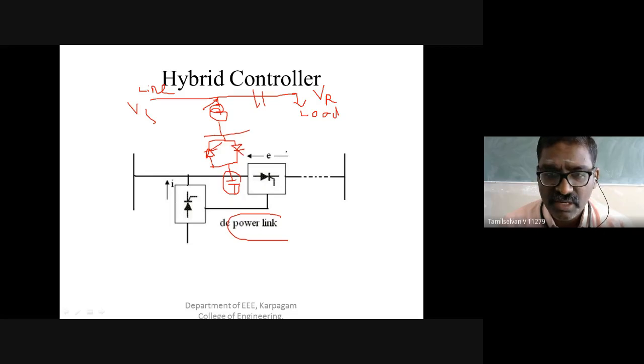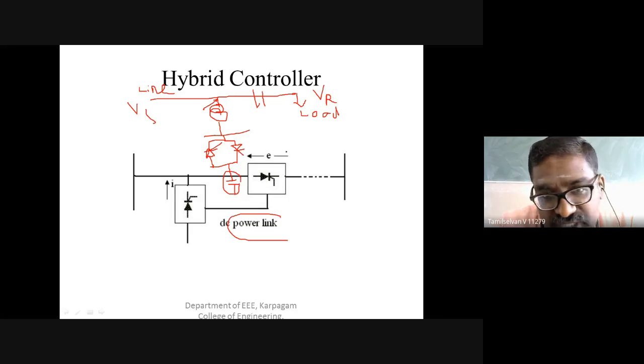That is called your hybrid controller. So here you have to know about each and everything. Suppose if I use the series capacitor, what does it control? It will control only the impedance. Suppose I'm using shunt capacitors - shunt reactors, load changing transformer, or synchronous phase modifier - it will control only the voltages.